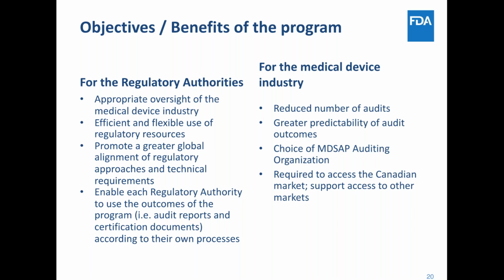The FDA accepts MDSAP audit reports only as a substitute for FDA routine inspections. However, all other situations listed under the FDA's compliance program guidance on inspection of medical device manufacturers still apply. For example, for cause inspections, when there is an identified issue with a product or claim, for pre-market inspections as part of the product assessment, or post-market inspections when there are commitments from the manufacturer that need follow-up, among others, we still need to conduct inspection. We do not accept MDSAP audit reports as a substitute for this kind of inspection, okay?